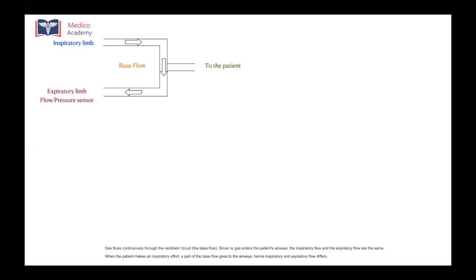Once the expiration is over, there is no flow occurring to the patient. So at that time there is something called a base flow, which occurs between the inspiratory limb and the expiratory limb of the ventilator. That is, gases flow continuously through the ventilator circuit when there is no flow to the patient. That flow is called the base flow. Usually it's around 10 liters per minute, suppose.